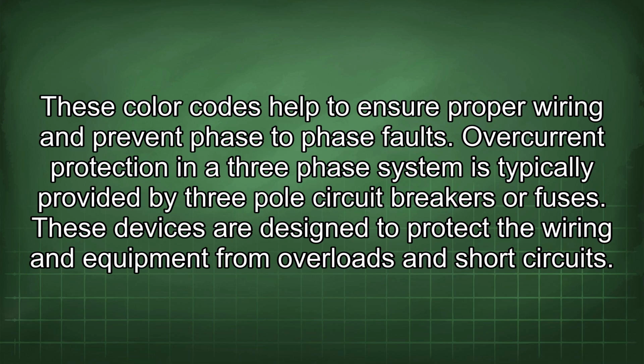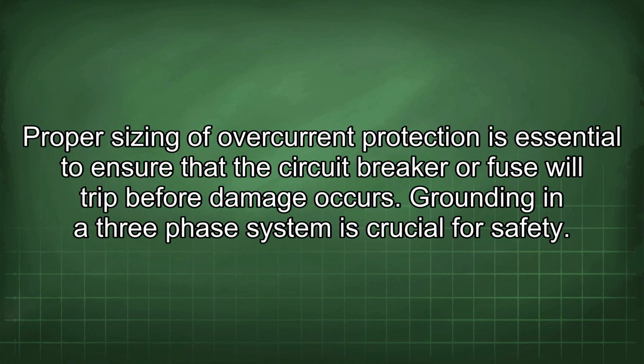Overcurrent protection in a three-phase system is typically provided by three-pole circuit breakers or fuses. These devices are designed to protect the wiring and equipment from overloads and short circuits. Proper sizing of overcurrent protection is essential to ensure that the circuit breaker or fuse will trip before damage occurs.